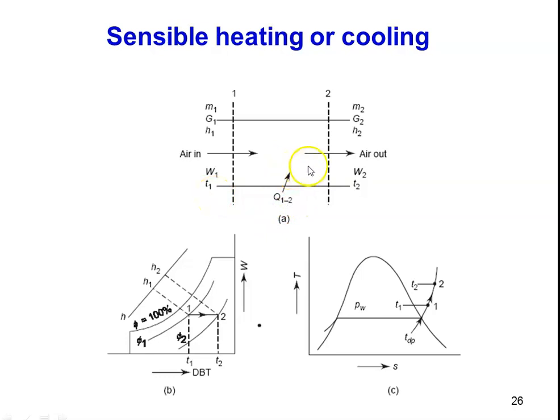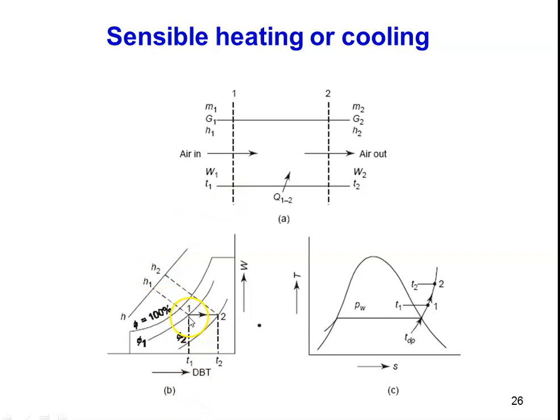Looking at the psychrometric chart, the initial condition has dry bulb temperature T1, relative humidity φ1, and enthalpy H1. The process is sensible heating from state 1 to 2, where heat is added to the air. There is no change in specific humidity of the air — sensible heating means increasing the temperature of the air without change in specific humidity.